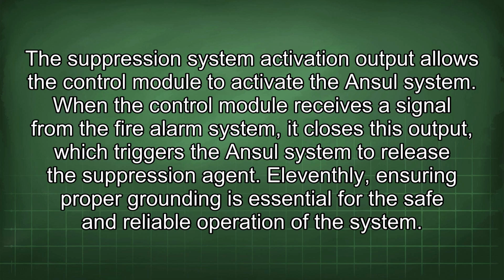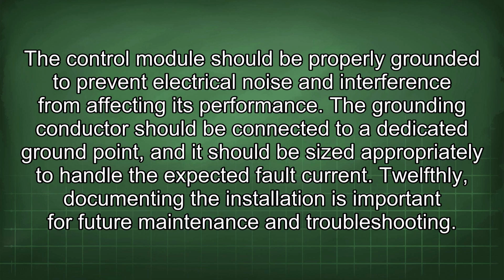11thly, ensuring proper grounding is essential for the safe and reliable operation of the system. The control module should be properly grounded to prevent electrical noise and interference from affecting its performance. The grounding conductor should be connected to a dedicated ground point, and it should be sized appropriately to handle the expected fault current.